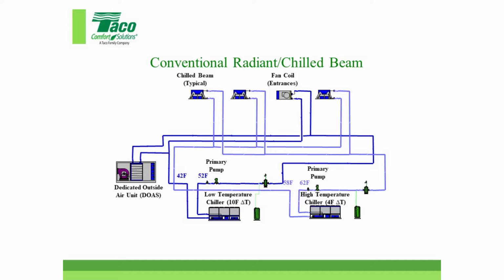We only show 1 pipe going around. We are mixing at the zone. This is our low flow block right here. So somehow you got a supply and return getting into the dedicated outside air, right off the chiller, 42 degrees, takes care of the humidity, the dew point. Then we mix at each zone. I'm going to get into the details of what this contraption is very shortly.